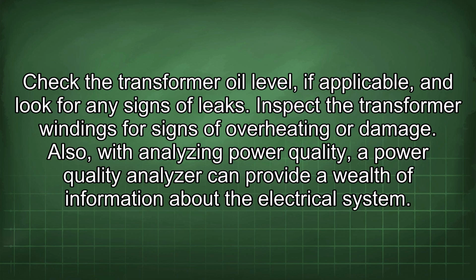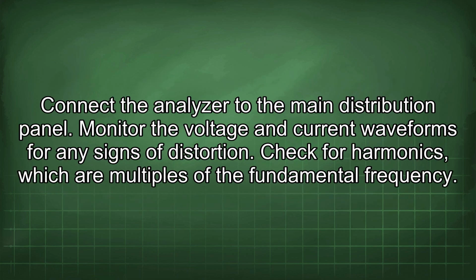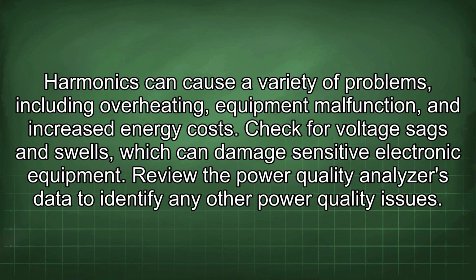Also, with analyzing power quality, a power quality analyzer can provide a wealth of information about the electrical system. Connect the analyzer to the main distribution panel. Monitor the voltage and current waveforms for any signs of distortion. Check for harmonics, which are multiples of the fundamental frequency. Harmonics can cause a variety of problems, including overheating, equipment malfunction, and increased energy costs.